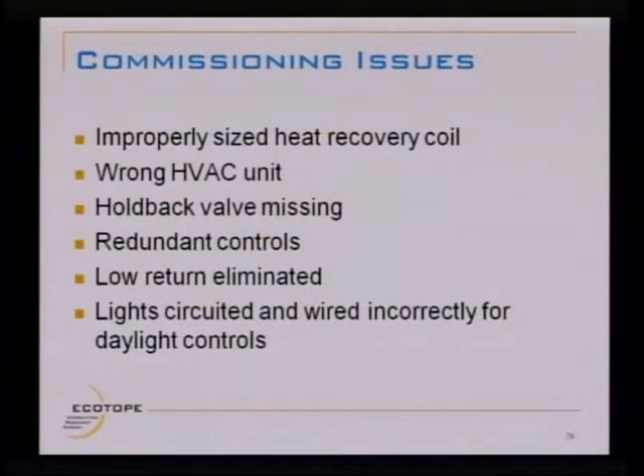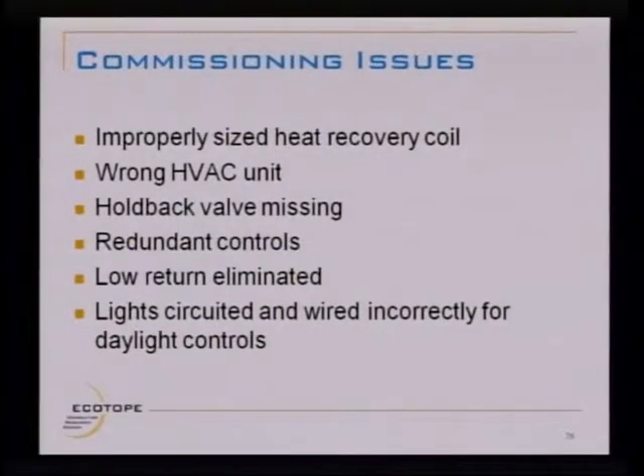He went to his standard commercial HVAC equipment supplier, told him what he wanted. They selected a unit designed as a VAV unit for an office building, essentially. Constant temperature, variable volume air handler, when what we wanted was exactly the opposite: variable temperature, constant volume. And they sent it off for an aftermarket coil, copper coil for the heat recovery coil, and they put in a coil that would be typical for hot liquid, like hot water to run through or something, not realizing that it needed to take a gas and then condense it to a liquid in the coil. So that coil had to be changed out, which cost an awful lot of money.